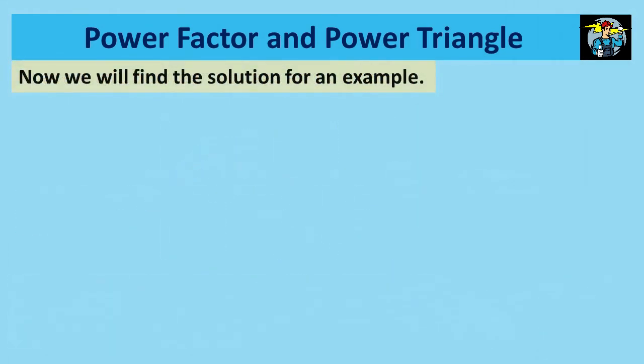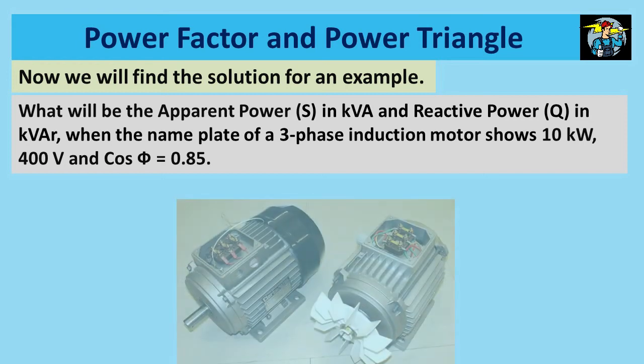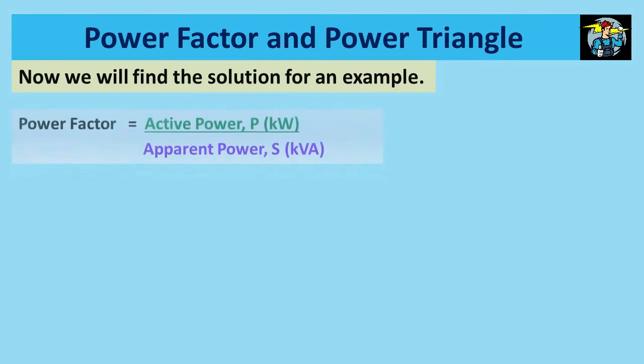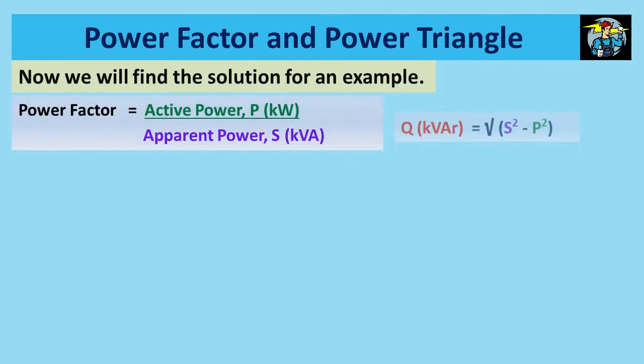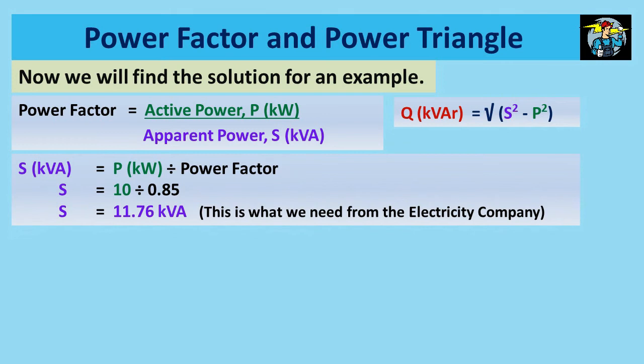Now we will find the solution for an example. What will be the apparent power S in kVA and reactive power Q in kVAr, when the nameplate of a three phase induction motor shows 10 kW, 400V and cos phi equals 0.85? These are the two equations to be used here. Power factor equals active power divided by apparent power. When we rearrange to get apparent power to the left side, it equals active power divided by power factor.